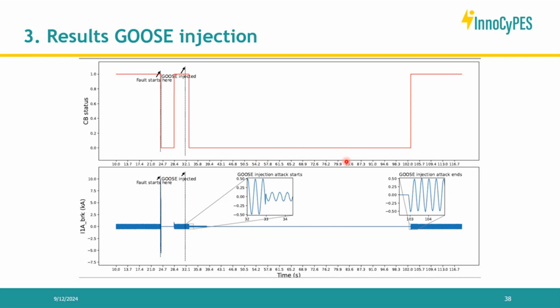When we injected a false tripping for the physical IED, for some reason we can't fully understand, given that the physical IED is a black box to us, its implementation added a delay of almost 1 minute to the reclosure mechanism. That circuit breaker took over 1 minute to reclose instead of just a few seconds. That was a very unusual behavior we observed because of the goose injection attack on the physical IED.